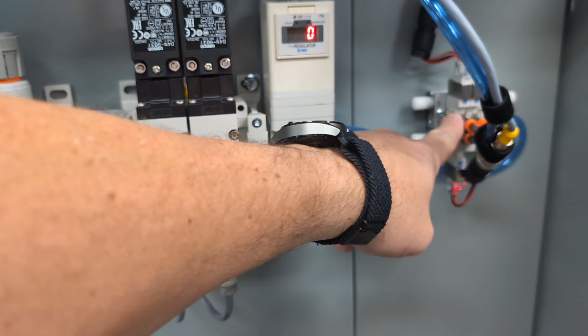All that work finally gets us to where we can test our output. This is our output module. I pressed the E-stop, and we see it dropped out. Now with that safety relay working, that gives us our outputs. Maybe we'll get a flashing light up there, we'll test it in a bit. That gives us our 2 air dump solenoid valves, which means, hopefully, we've got pressure here. I believe we probably do. So now I need to get the I/O link up and going so I can get pressure to these solenoids to get that moving. But let's test the rest of the outputs first, then we'll come back to this.